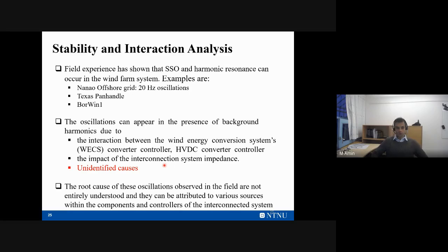For example, the current standard for renewable energy or distributed generating units like wind tries to keep the short circuit ratio—the strength of the grid—around 10. But when you have much more renewable energy, it's not possible to keep the short circuit ratio at 10. It reduces a lot, meaning the grid impedance is much higher, so they can interact with the grid.